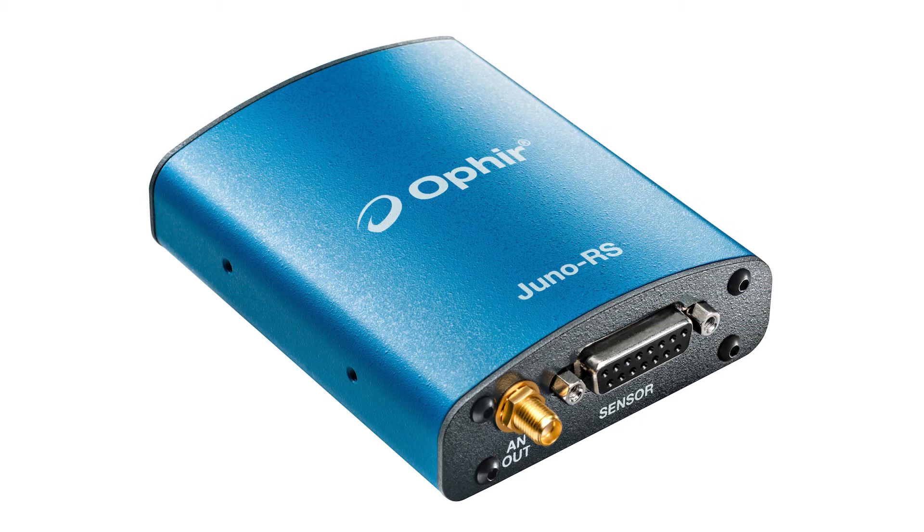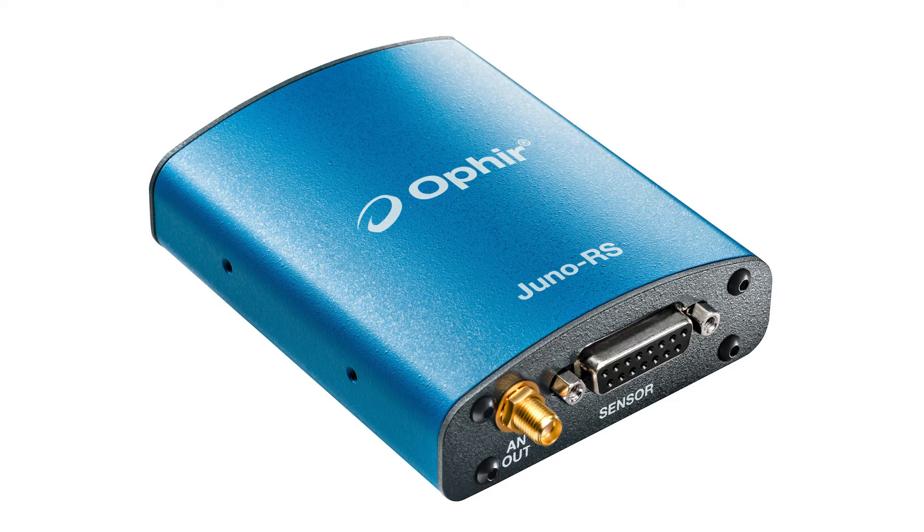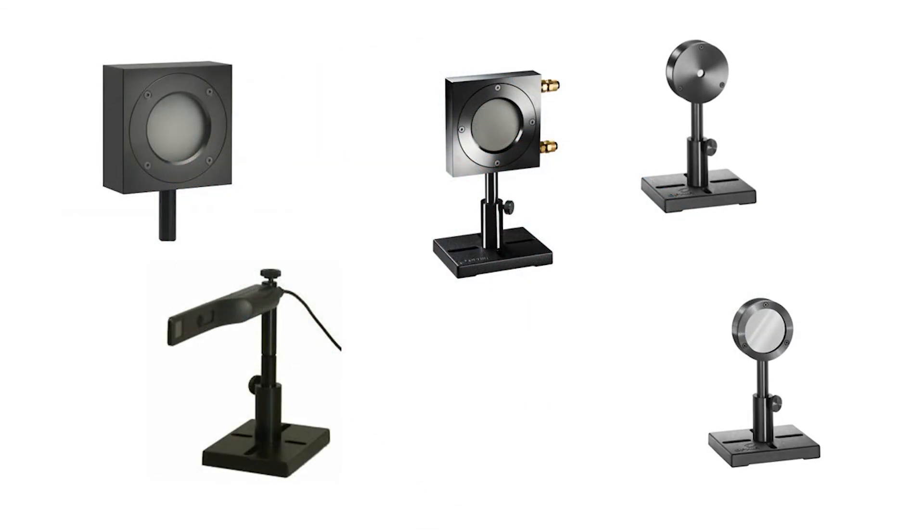The new Ophir Juno RS may be just the solution. The Juno RS is a virtual meter that enables connecting any of Ophir's standard power and energy smart sensors to automation systems and computers using RS-232 communication.